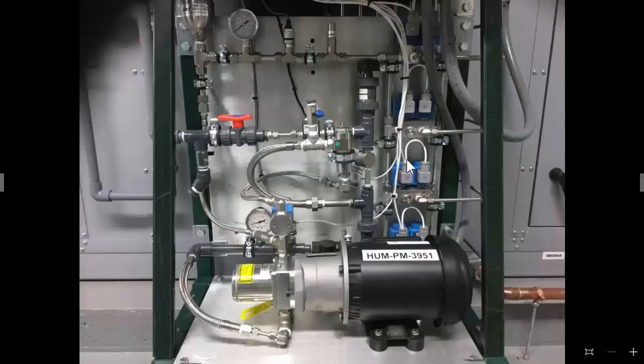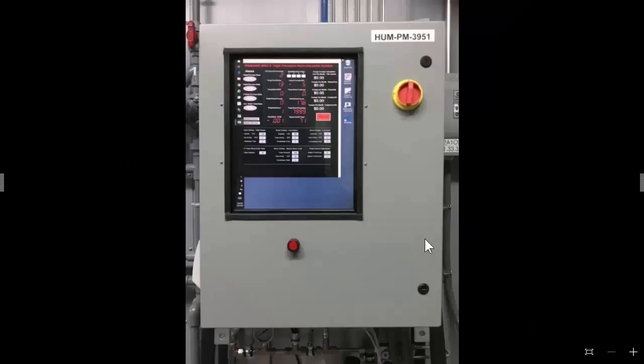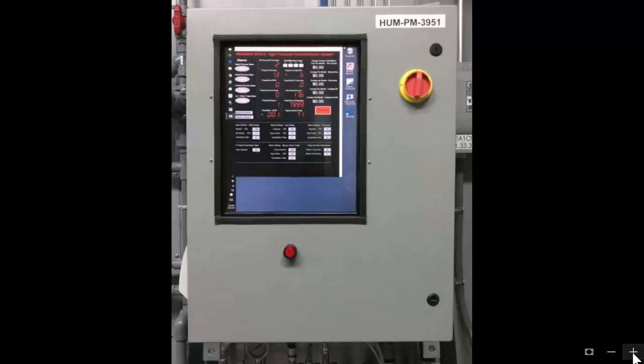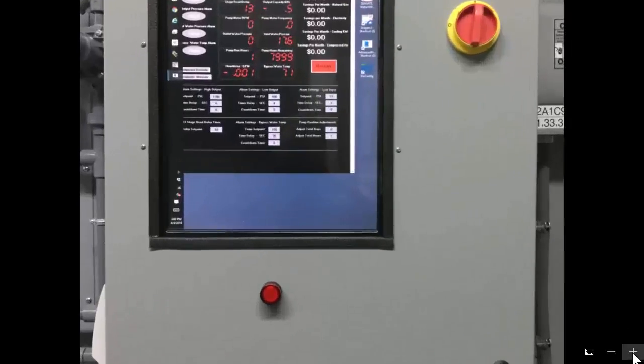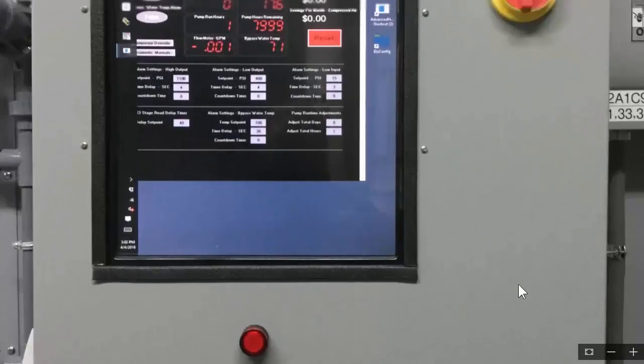If I think of anything else, I'll add it in, but what next we're going to look at is the alarm settings for this particular pressure transducer that monitors the high pressure. So here's the front display, and this is going to be similar to when we talked about the alarms for input low water pressure type alarms, or the input side, water coming in. So I'm going to zoom in here and adjust this a little bit.